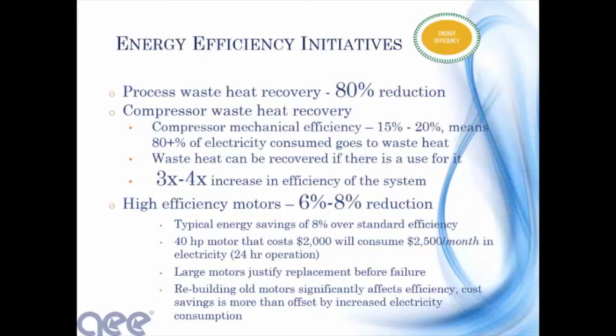Compressor waste heat recovery. This is something we're just getting into. We actually don't have any projects implemented yet, but if anybody's familiar with compressed air, it's a very expensive utility. It's notoriously wasteful and inefficient. So a typical air compressor will only take about 15 to 20% of the electricity put into it to actually provide any service for you, or move an air cylinder, provide any motion or utilization. So the other 80% of that electricity is all in the form of waste heat.